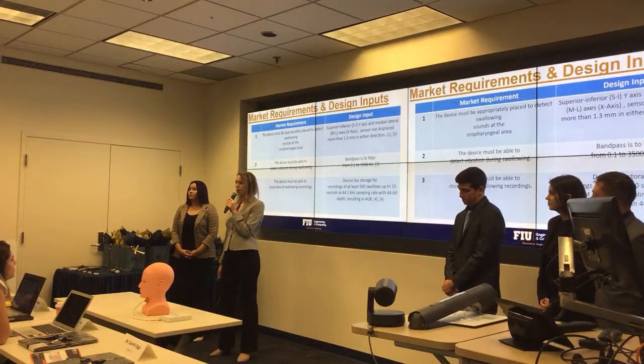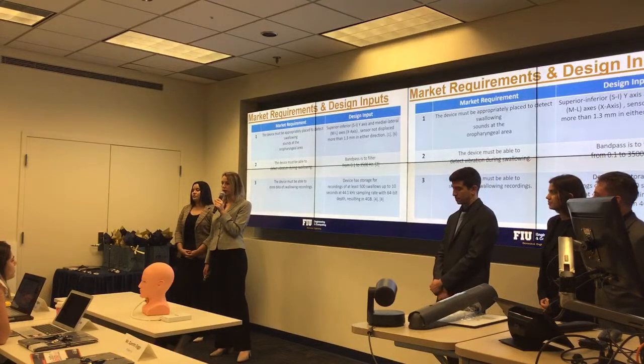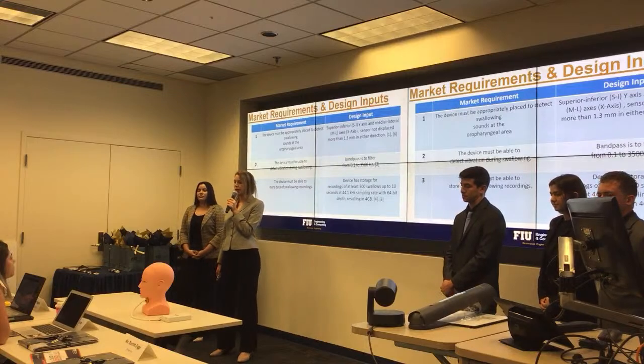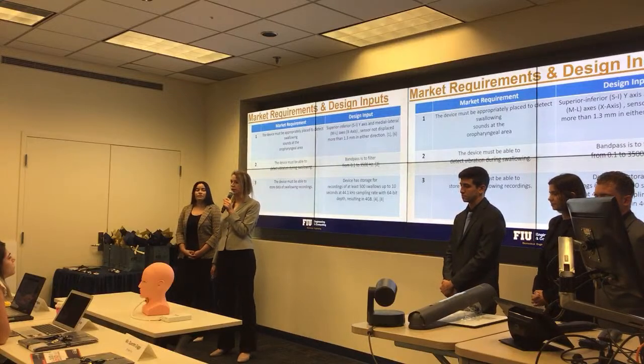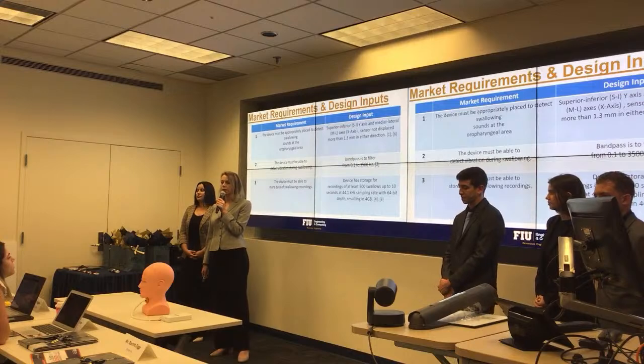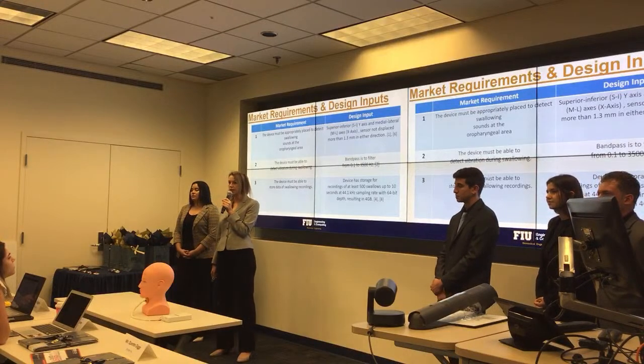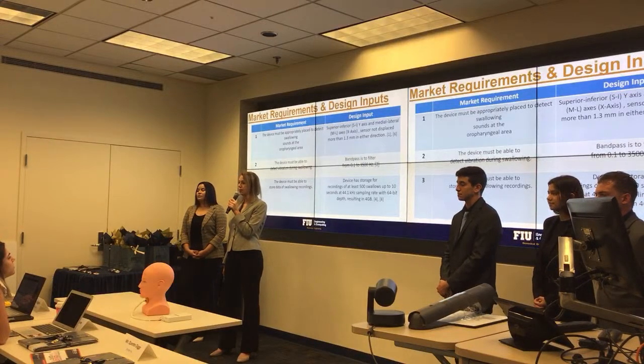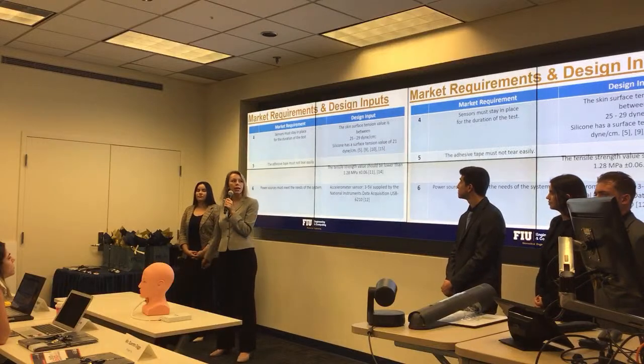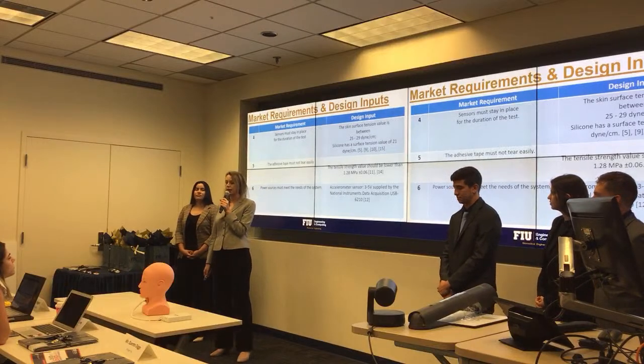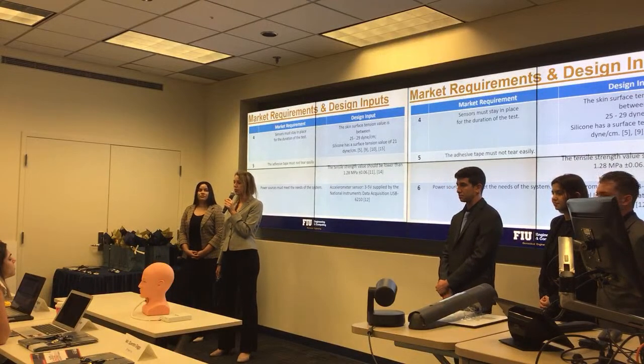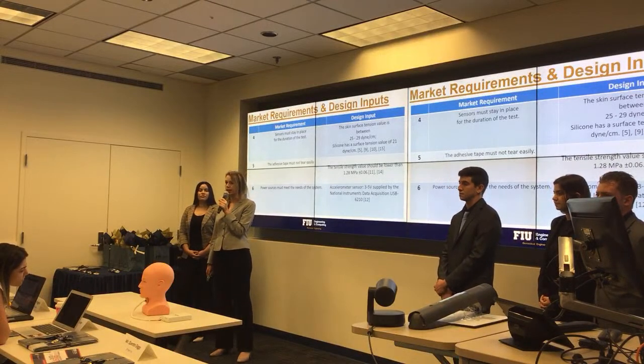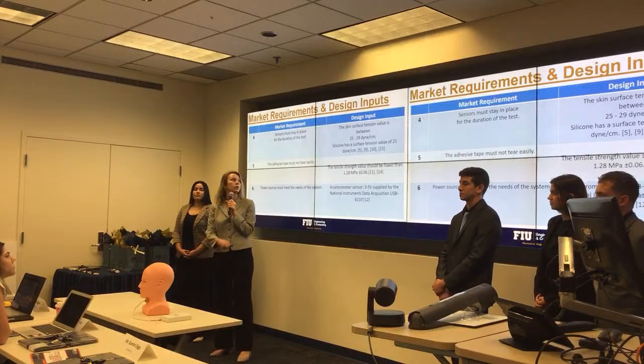So these are the market requirements and design inputs that we have for our screening device. We decided that the appropriate placement of our screening device is considered an important market requirement, as the sensor should not be displaced more than 1.3 millimeters. In addition to that, we decided that the adhesive tape that is attached to the screening device should not tear easily, as this will affect the placement of the device and cause patient discomfort.